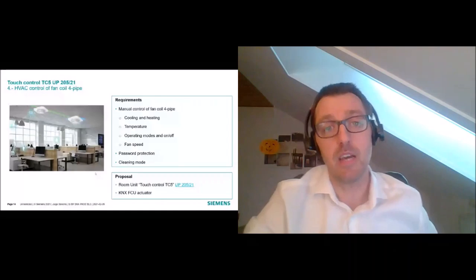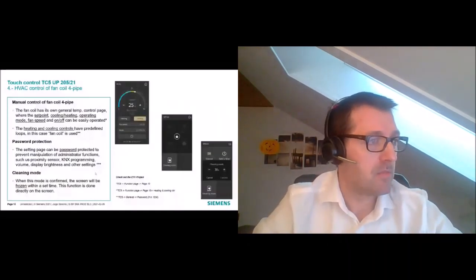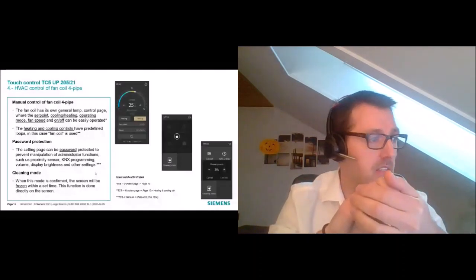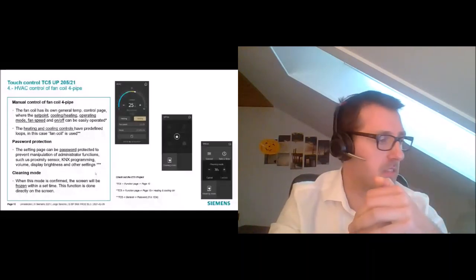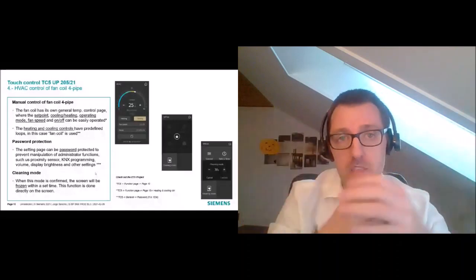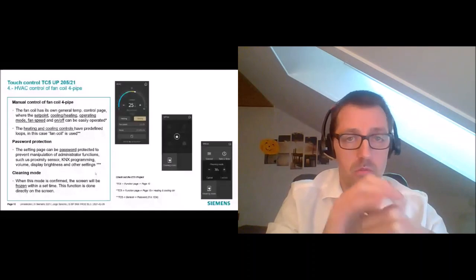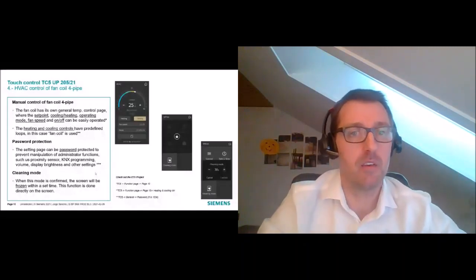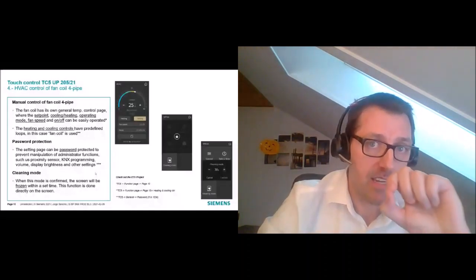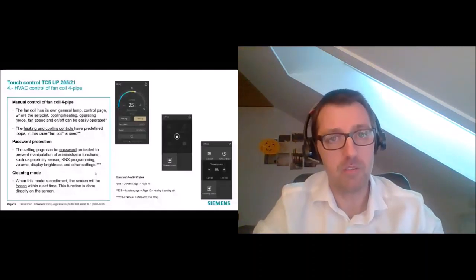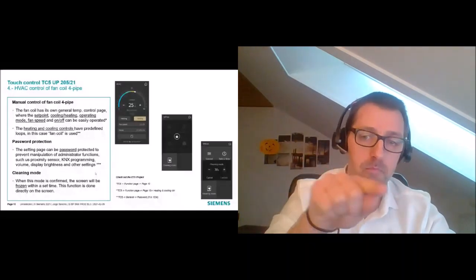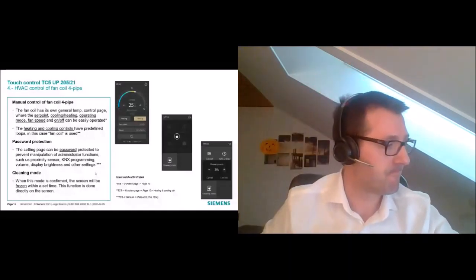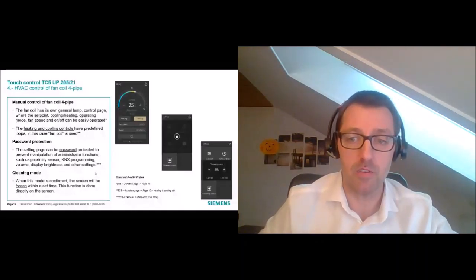Regarding password protection, the TC5 has a settings page that can be operated directly from the panel — used to enable KNX programming, the built-in proximity sensor, volume, brightness. You may want this protected with a password, so you simply set the password in ETS. Then only people who know the password can access the settings or administration page directly on the TC5. The only thing not protected is the cleaning mode, which is always available: cleaning staff can press the button and during a set time the screen is frozen so it can be cleaned easily.